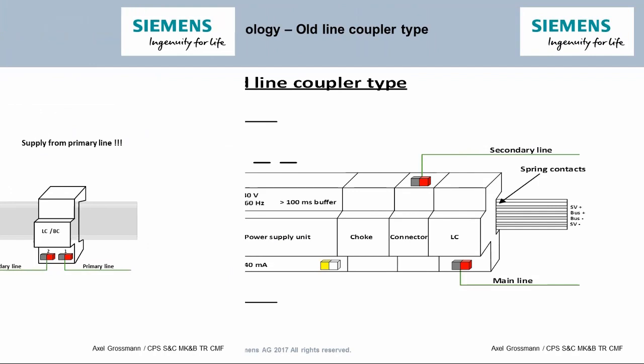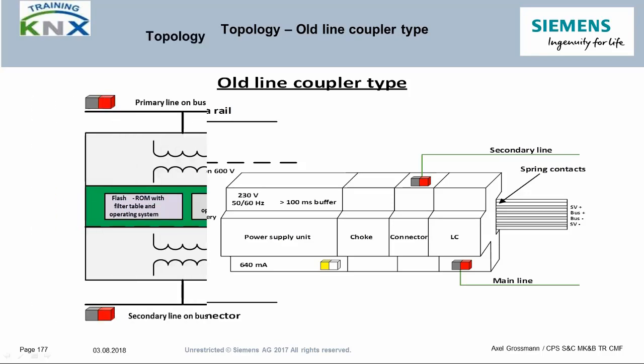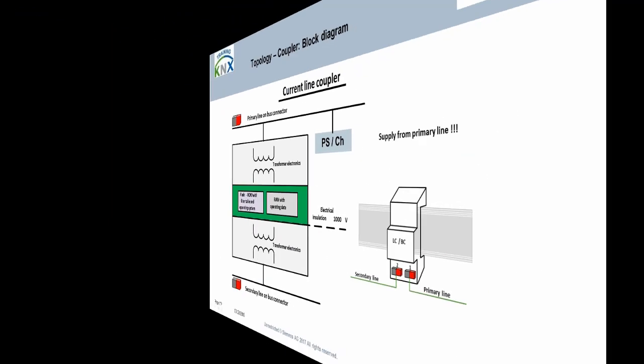It wasn't always like that. In the first couplers, filter tables were stored in a battery-backed RAM memory. These earlier couplers, if they can still be found in existing KNX plants, should all be replaced, as they have not been manufactured since 2003, and therefore even the longest-lasting batteries are likely to be flat by now.